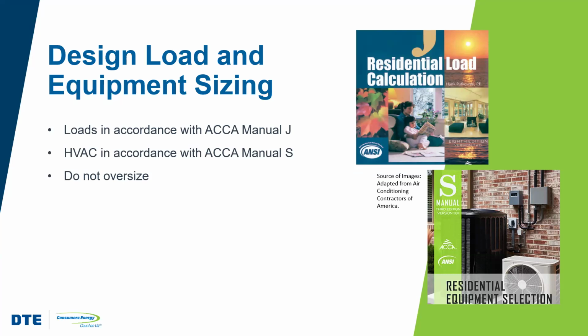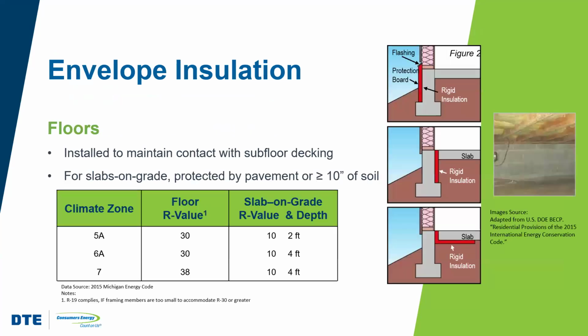And also, larger equipment has a higher first cost, which is never good for the homeowner. So a good design uses properly sized equipment to meet the anticipated load, and that equipment has the ability to modulate to closely match the load as it changes throughout the year and over the course of a day. Now, the load estimate and the equipment sizing are calculated in accordance with manuals J and S, respectively, from the Air Conditioning Contractors Association. Now, these manuals outline in detail the necessary data and the steps needed to accurately determine the home heating and cooling requirement and the appropriate equipment size to meet that requirement efficiently and economically.